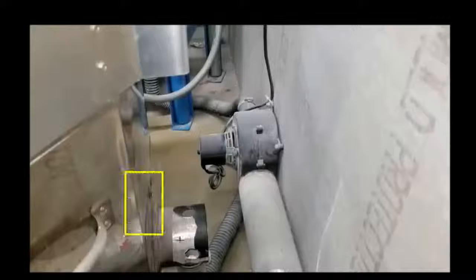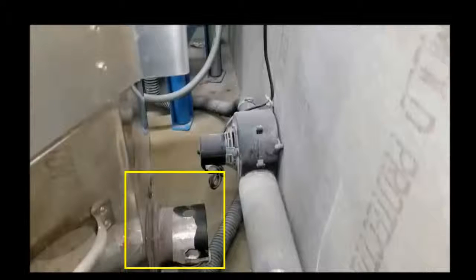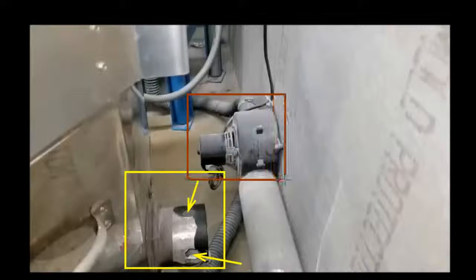So if I look really closely here, I have a pickup. And if I look even closer, that pickup brings in room air and it mixes the room air in this mixing manifold, so it keeps the air well below 140 degrees. It has a single exhaust blower here, a pretty nice blower. But all these things are rated for less than 140, 150 degrees, unless you buy something real specialized.